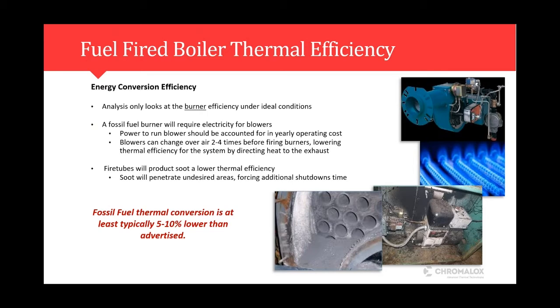So as these systems operate, especially with a coal fuel source, you can get a lot of what's called soot that builds up on those elements, the heat transfer area, which basically reduces the capability of those systems to take that applied heat and put it into the process. So you lose some efficiency that way. And one thing that's not considered as well is the use of electric power to run these systems, because the blowers run through pre-purge and post-purge runs to clear out those gases before the flames are energized. So there is some electric use that gets factored in. That's very infrequently factored into your total cost of fuel operations. So certainly something to be considered as well.